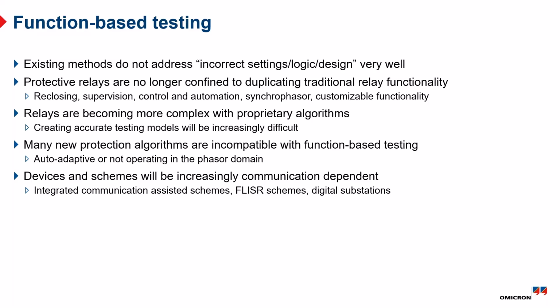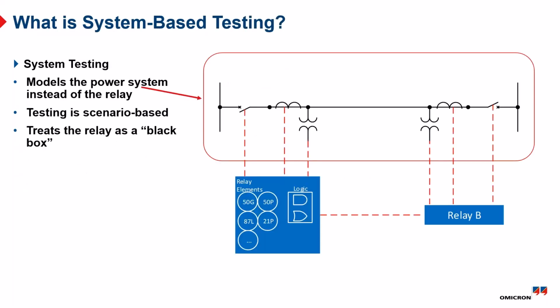As these devices become more sophisticated and communication dependent, you have to not only simulate voltage and currents to the device, you also have to simulate any incoming communication with the device in order to test that particular function. And this is becoming obviously more and more common.